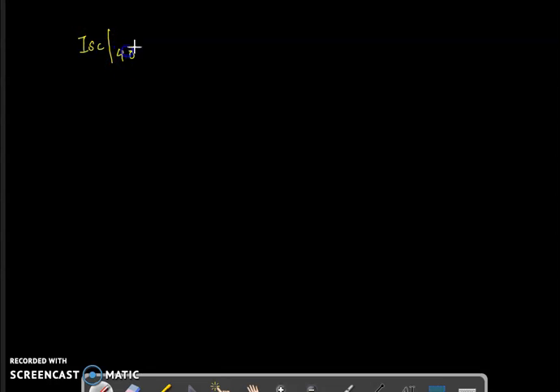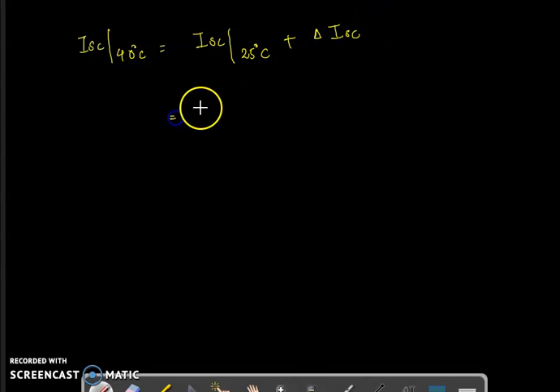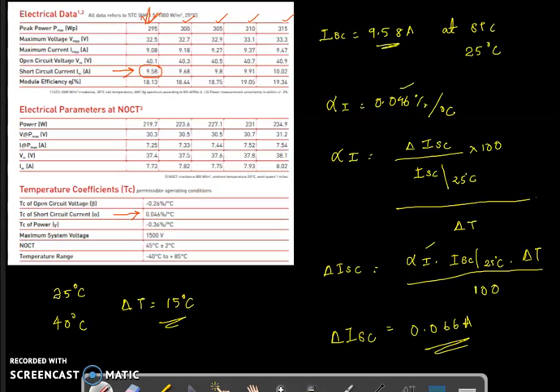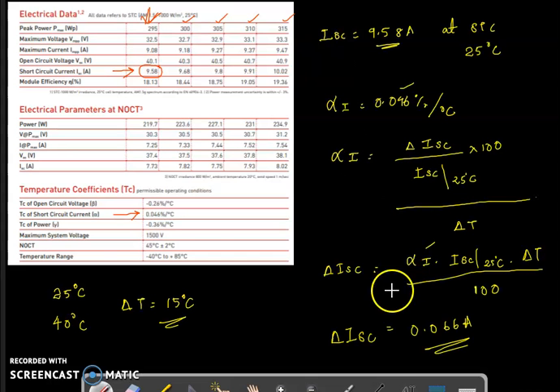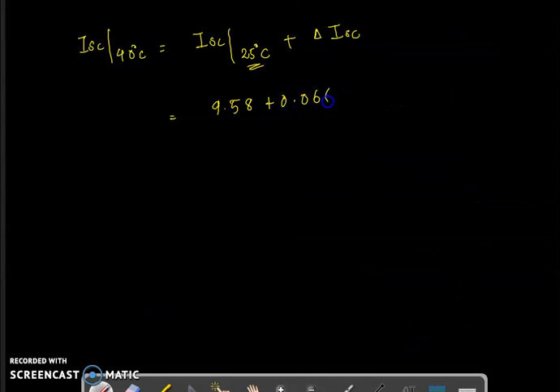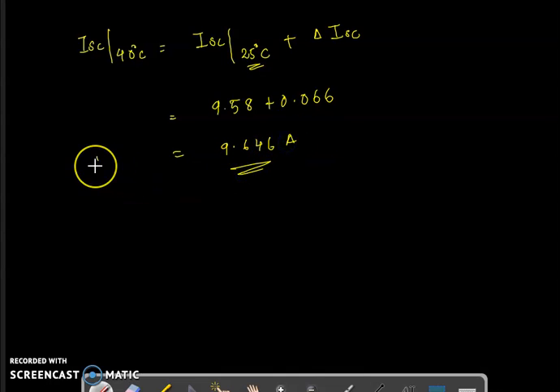The short circuit current at 40 degrees Celsius equals the short circuit current at standard test condition plus the change in short circuit current due to the change in temperature. So that is 9.58 plus 0.066 amperes, giving a final answer of 9.646 amperes. This is the short circuit current of this panel at 40 degrees Celsius.